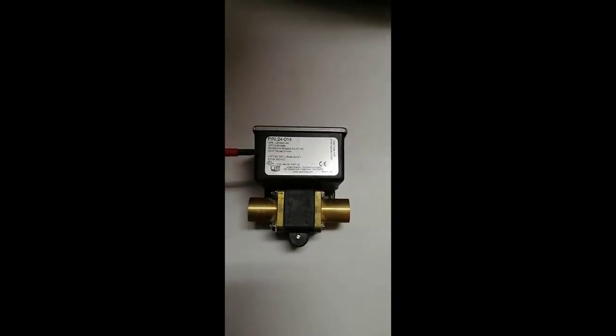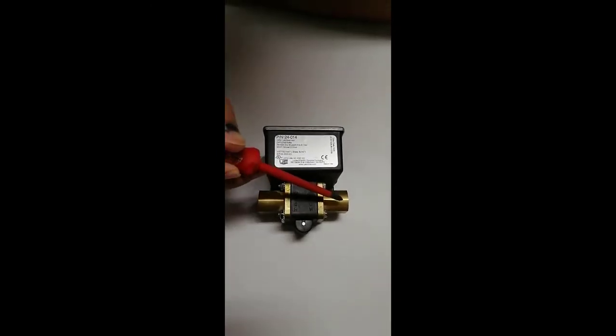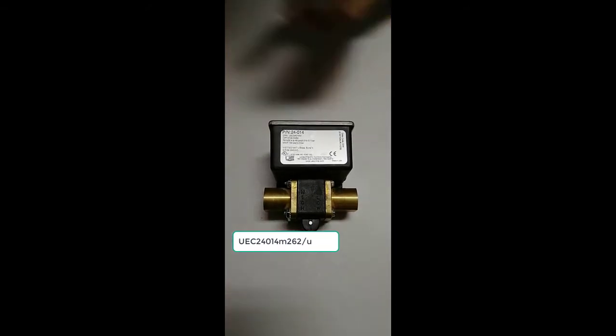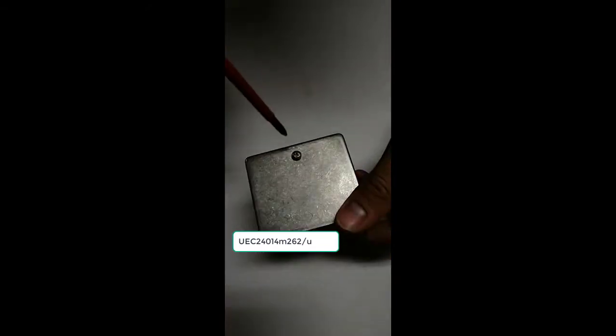This is water differential pressure switch. We use it across chilled water pumps to know the flow. Okay, it has two ports. This is high pressure port and this is low pressure port, and the part number I will mention in the video. And then we can open this to make the connections.